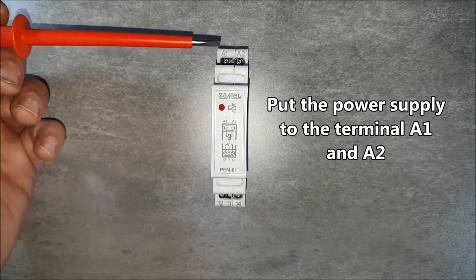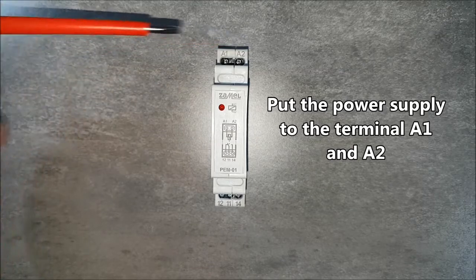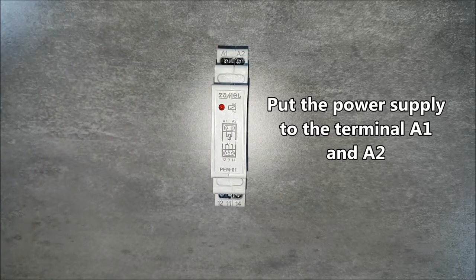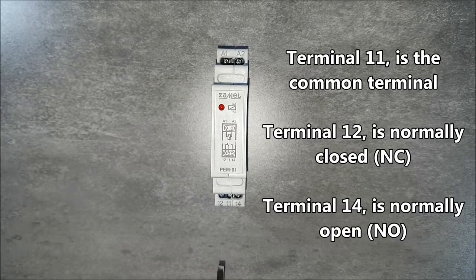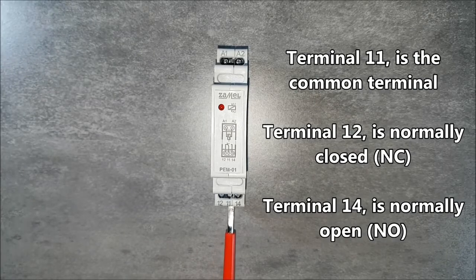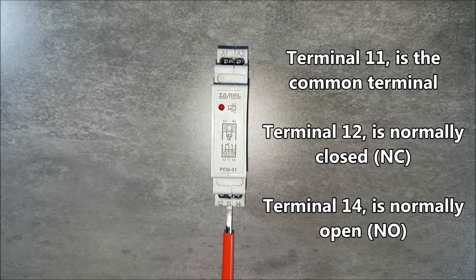The device has power terminals A1 and A2. Supply voltage 12 volt AC or DC is applied to these terminals. At the bottom of the device are relay outputs. Terminal 11 is the input terminal of the relay. Terminal 12 is normally closed. Terminal 14 is normally open.